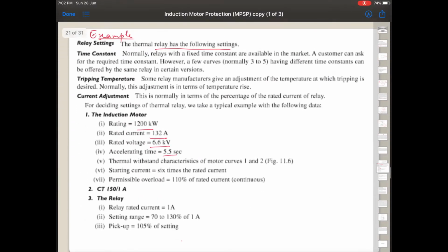Now coming back to the example, we have a CT ratio of 150/1, that is, primary current is 150 and secondary current is 1 ampere for the current transformer. The relay is connected to the secondary of the CT, so the secondary current is rated 1 ampere, so the relay is also rated as 1 ampere. Then the setting range is somewhere between 70 to 130% of 1 ampere, that is 0.7 ampere to 1.3 ampere, and pickup is generally more than 100%.